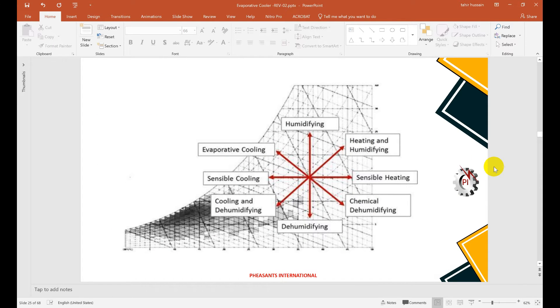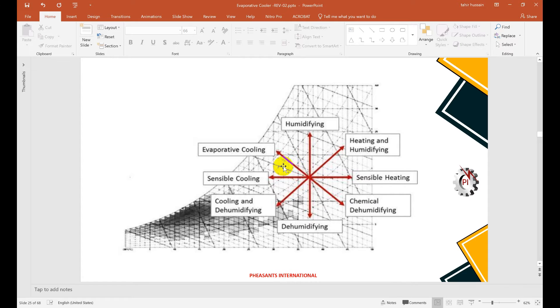On the psychrometric chart: moving straight to the left decreases sensible heat — that is a cooling process. Moving straight to the right increases sensible heat — that is a heating process. Moving straight up adds moisture — that is humidification. Moving down is dehumidification. A conventional air conditioning system operates in the region involving both cooling and dehumidification, or cooling with humidification.